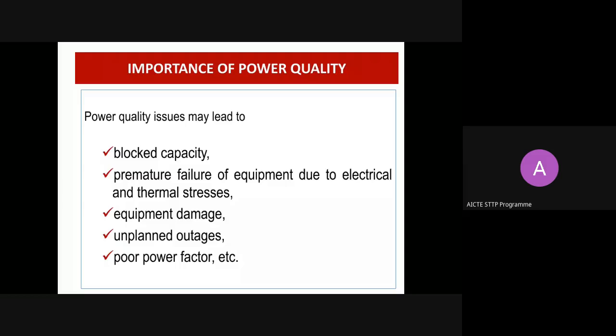And then the equipment connected in the system, whether it's a transformer or reactor, whatever electrical equipment we connect to the grid, is designed to operate at fundamental frequency. But when you inject current at frequencies other than the fundamental frequency, what will happen? This will damage the electrical equipment, often because of thermal stresses. That leads to premature failure of the equipment.